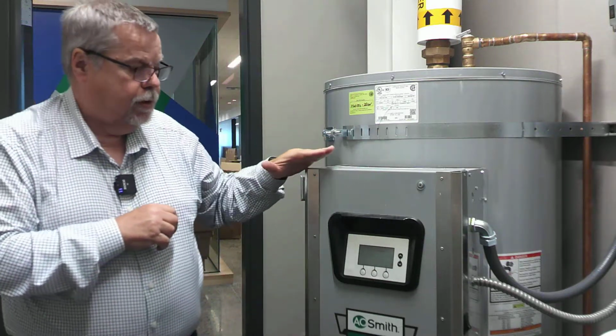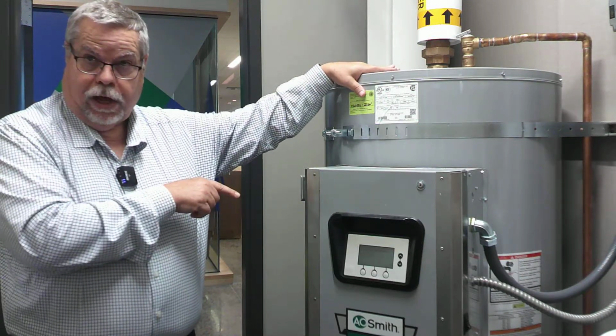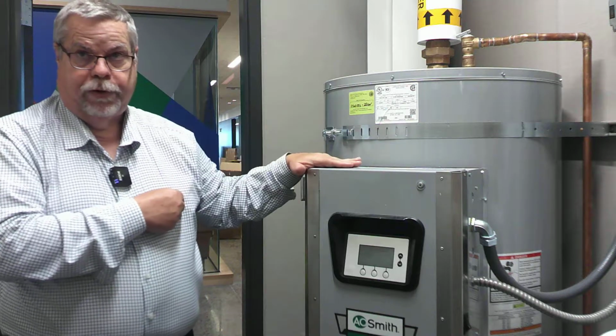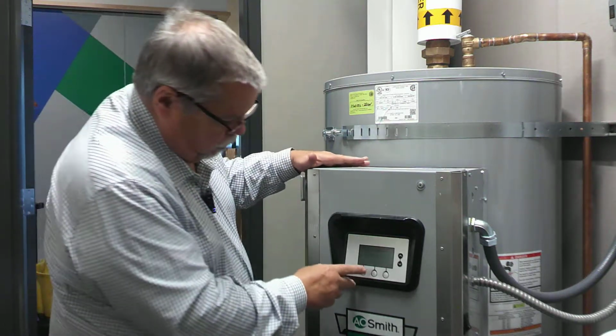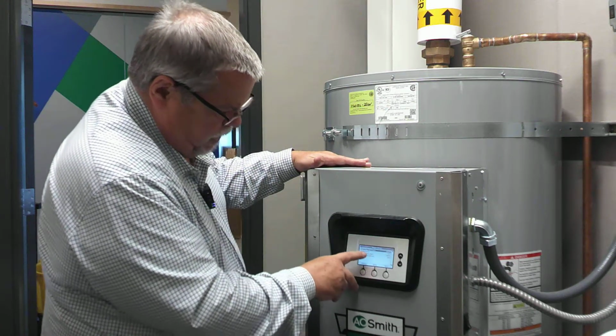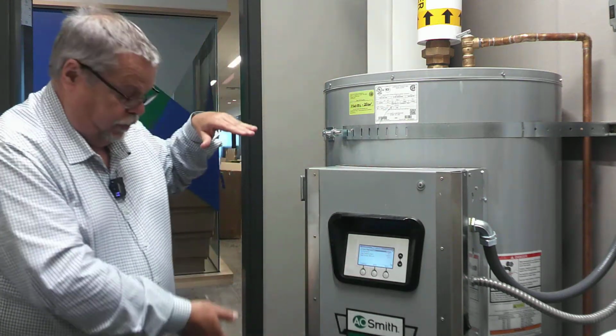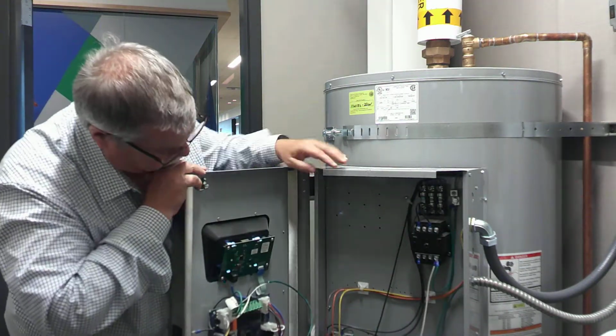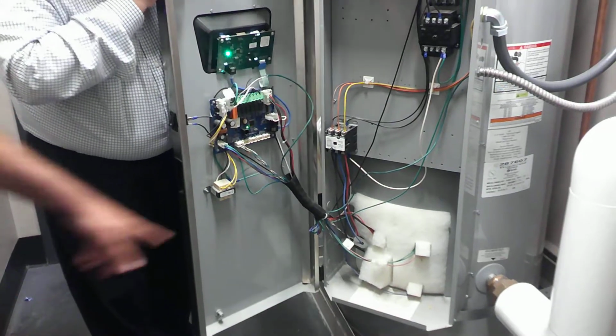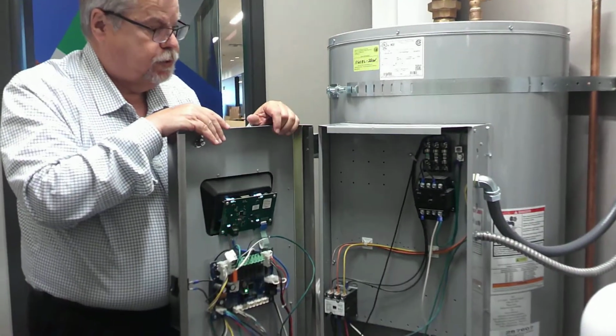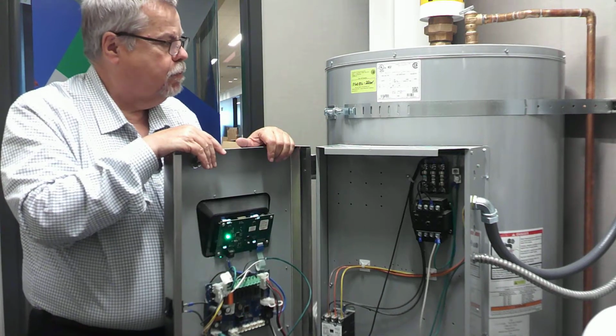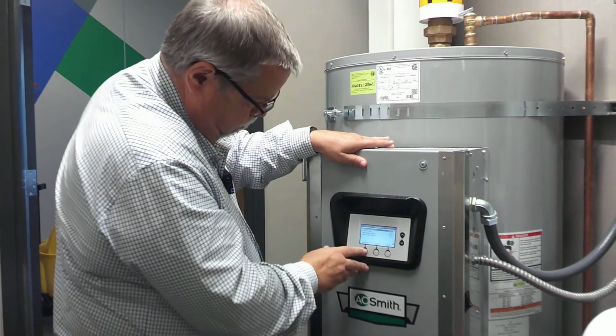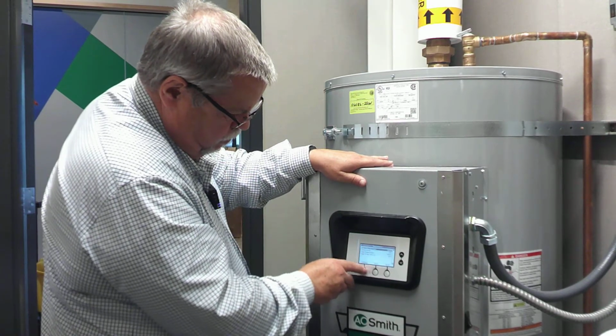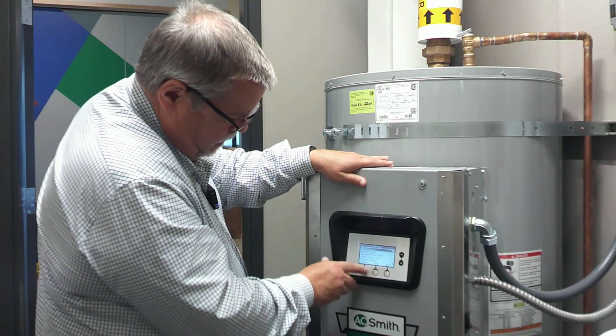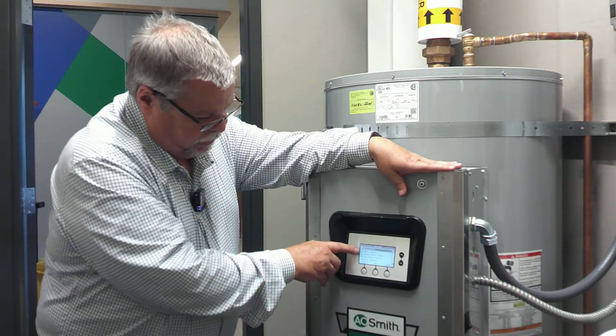So this water heater, once it heats up to 120, the control will shut off. It won't turn back on until it drops 3 degrees. Both the temperature setting and the differential are adjustable in the field. It's got a tank probe, so to get that 120 degrees, it takes temperatures in 2 places, on the top of the water heater and through a tank probe down there. All these parts are replaceable. We do stock parts over at Hollabaugh Brothers for emergencies, or they can come from the factory. Once you change a temperature here, you put a change and then you'll set it. We'll go back. Some of the other things you can do are the heater status.